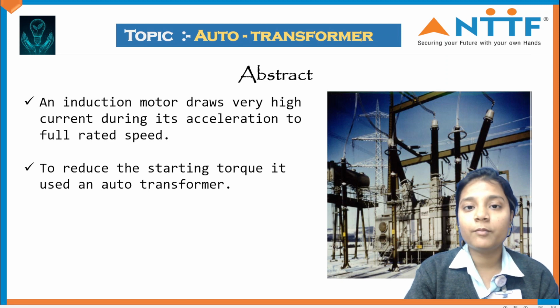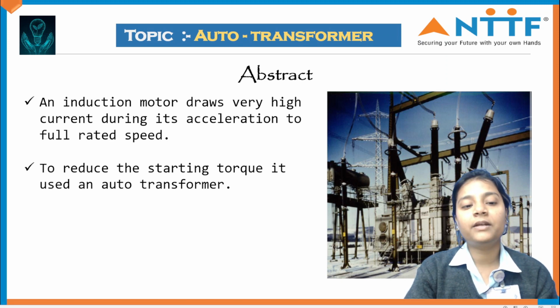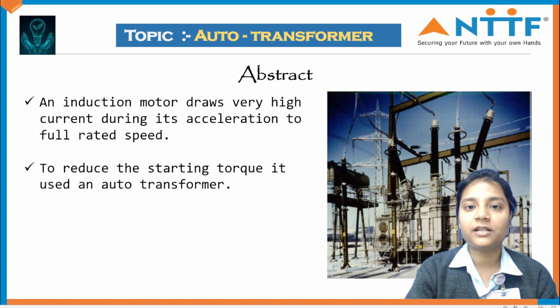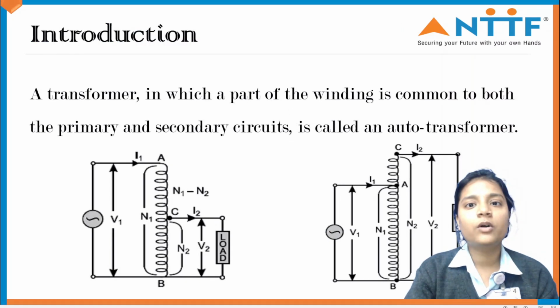An auto transformer is generally used in application of an induction motor, as an induction motor draws a very high starting current, generally 6 to 10 times greater than the full rated capacity. So we use an auto transformer for the starting of an induction motor with the tappings at 60, 70 and 80%. So what is an auto transformer?